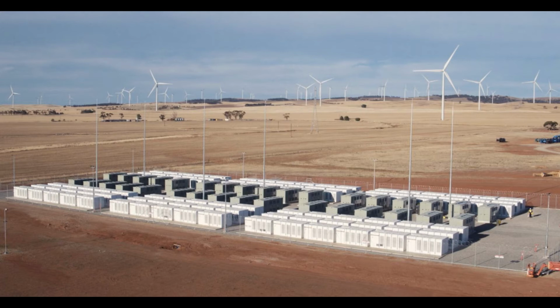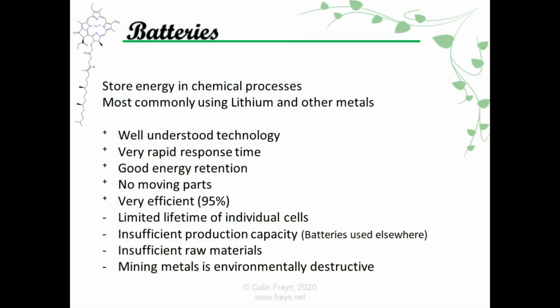That capacity would power roughly 10,000 homes for a day. The battery is primarily used to store power from the neighbouring Hornsdale wind farm, and it has already comfortably paid for itself, not only by storing excess wind power and avoiding having to switch the turbines off in times of high production, but also by helping to control the grid frequency by patching up mismatches between the energy supply and demand.